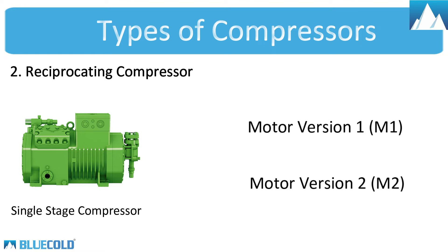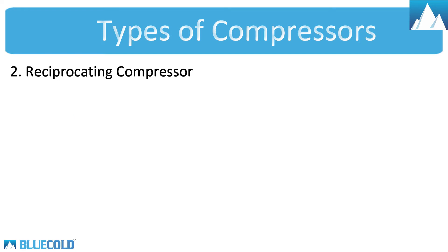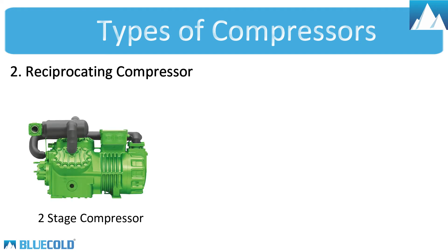Motor Version 2 — in technical sheets, it is denoted as M2. These models have smaller motors as compared to M1. It can be used only for negative temperature applications if you are charging R404A refrigerant in it. For R134A refrigerant, it can be used in both positive and negative temperatures.